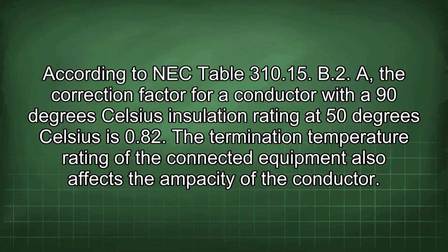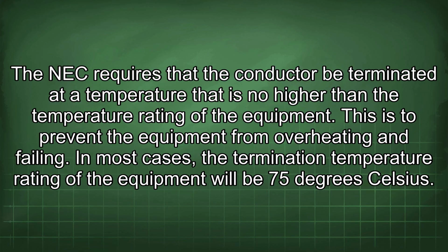The termination temperature rating of the connected equipment also affects the ampacity of the conductor. The NEC requires that the conductor be terminated at a temperature that is no higher than the temperature rating of the equipment. This is to prevent the equipment from overheating and failing.